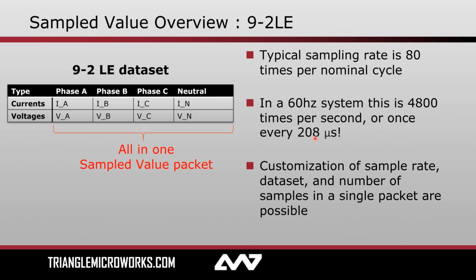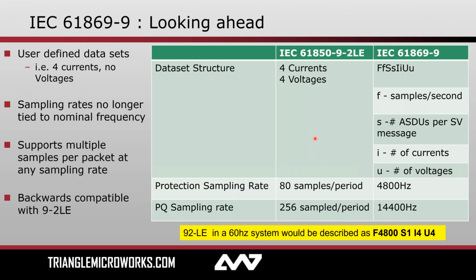Now, there's also in 9.2 LE a definition for power quality, which ups that sampling rate to 256 times per nominal cycle, giving us 15,360 samples per second. Again, that's useful for power quality applications. There is a newer variant on this, and that is IEC 61869-9. Both of these are sampled values, and in my experience, 9.2 LE is more widely available today, but 61869 is the way that things are headed.